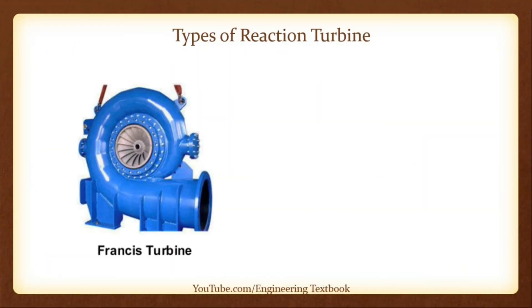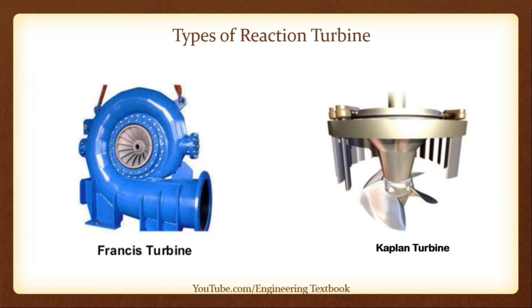Types of Reaction Turbine. Francis Turbine — this type of reaction turbine is an improved version of the propeller turbine, with water flowing radially and axially into the runner. In the middle section of a Francis Turbine, the flow is generally set in a spiral housing with adjustable guide vanes. Kaplan Turbine — Kaplan turbines can achieve high efficiency levels under various load conditions by properly adjusting the blades during operation. Kaplan turbines allow you to adjust the blade angle on the impeller according to the required power, enabling them to work efficiently under load changes.